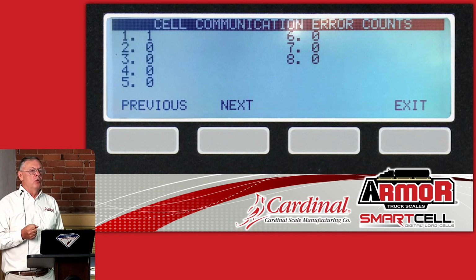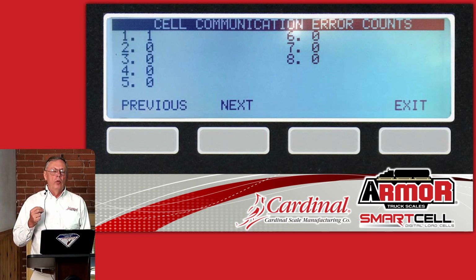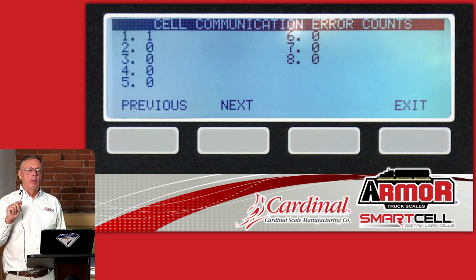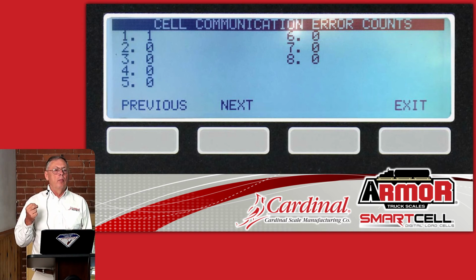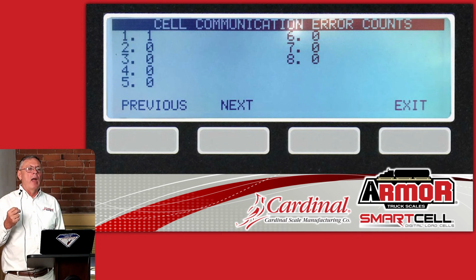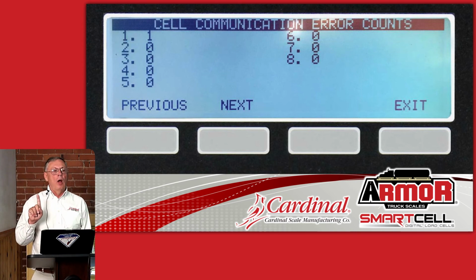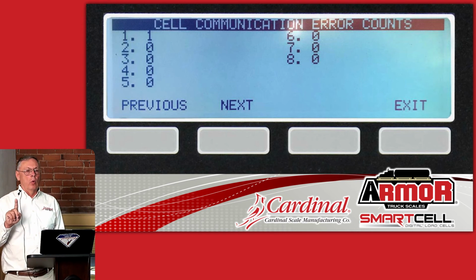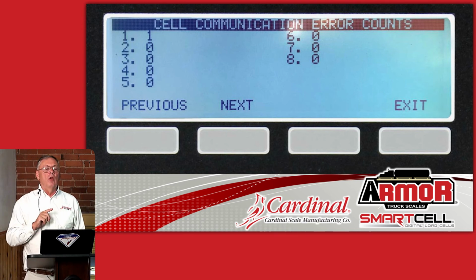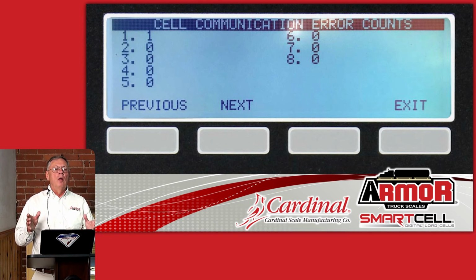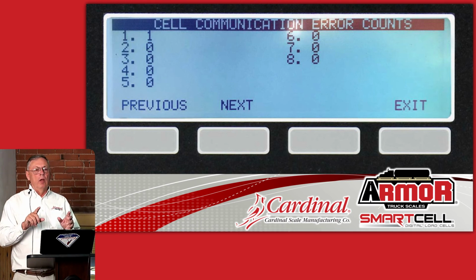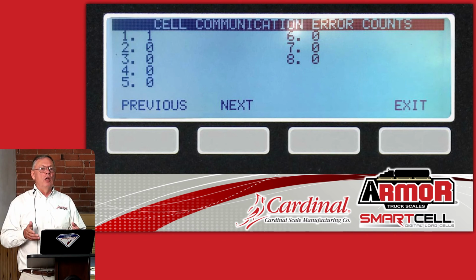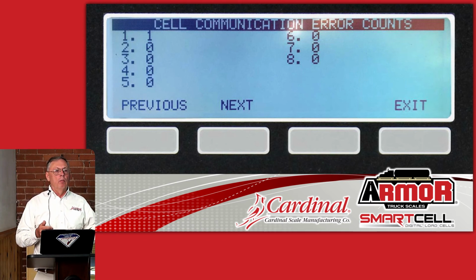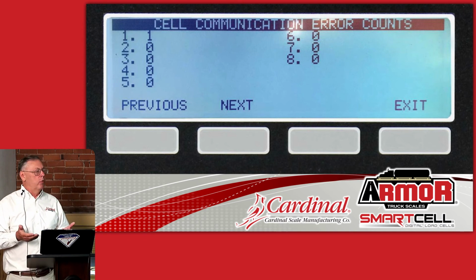One of the issues you can have with a digital load cell is it's not communicating. When the 225 indicator requests data from the load cell, we should get data back immediately. If we don't get that data back, just like here, load cell number 1 says, I've had one time that I didn't get data when I requested it. Now, sometimes at startup, when you first turn the scale on, you may throw some communication errors because the load cells may not start immediately at the same instant that the indicator starts asking for data. So after initial startup, you want to 0 this screen because you may throw a few errors initially and there's really nothing wrong with the system.